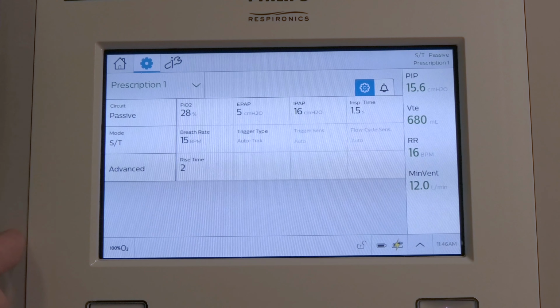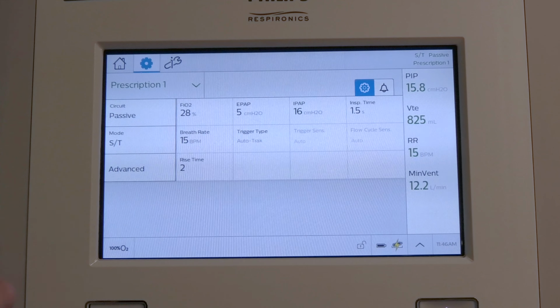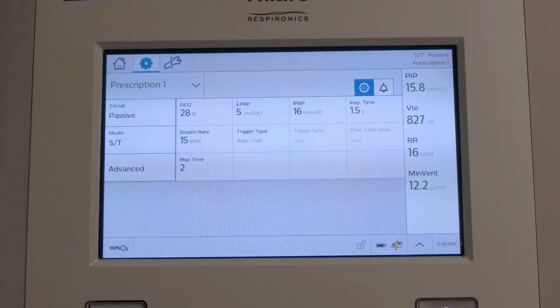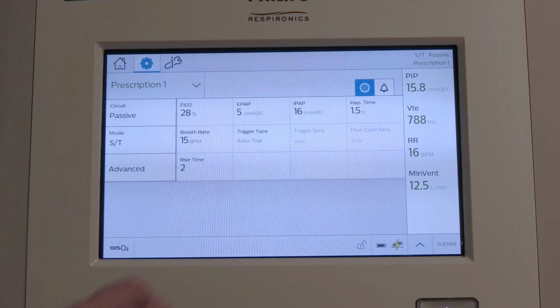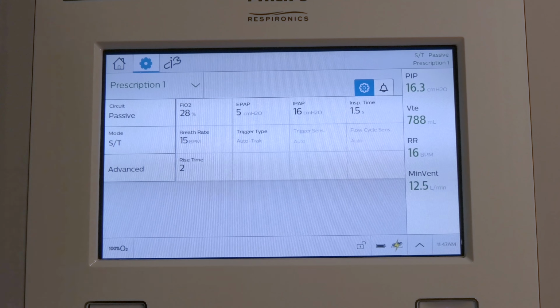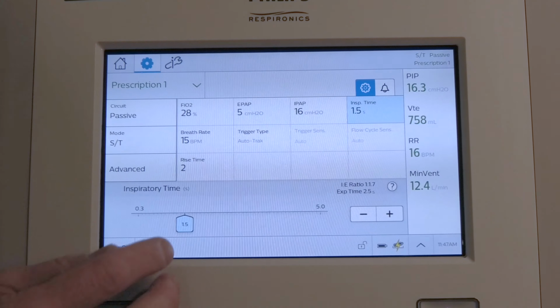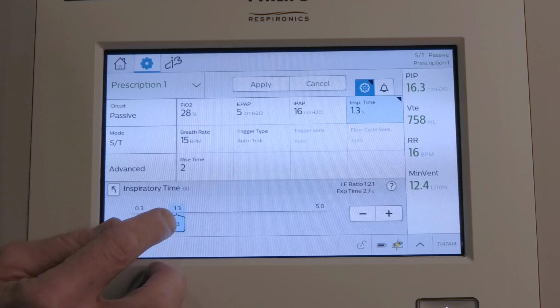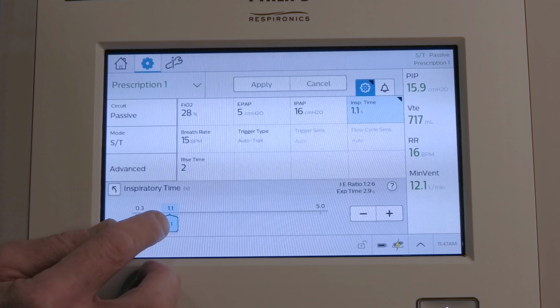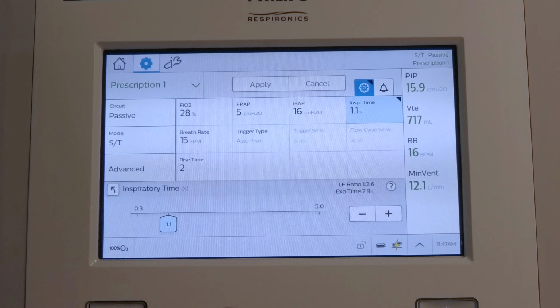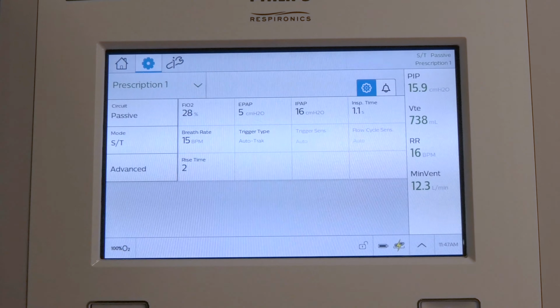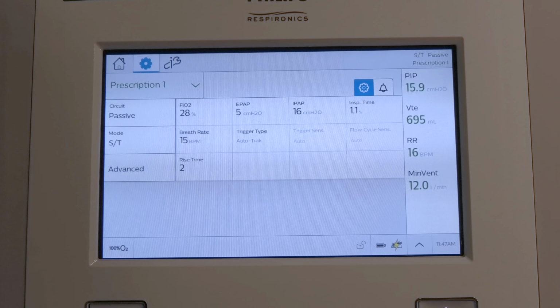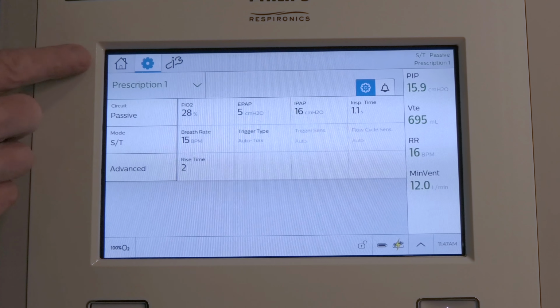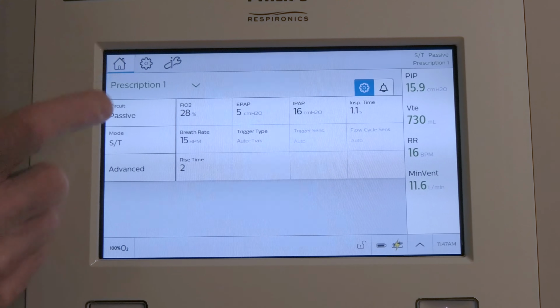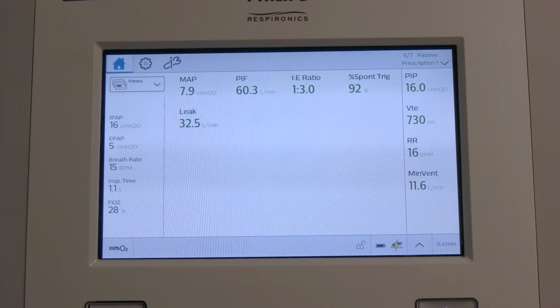So our inspiratory time tells the ventilator how long to breathe in or blow for on the backup breaths. When the patient is taking breaths spontaneously, the I time doesn't factor. So I would probably have my I time between 0.9 and 1 seconds for a backup rate of 15. Go to apply those settings. Once you're happy with what you've done, then you go back to your home screen and you're back in your monitoring screen again.